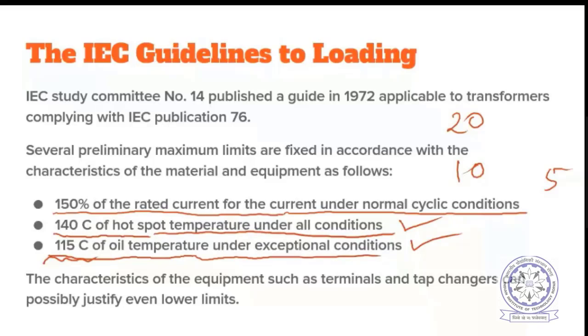the research being carried out by various labs, and the study committee investigations on this. So these are based on well-established results. The industry has to follow these to minimize the failures of the transformers. The characteristics of the equipment, such as terminals and tap changers, can possibly justify even lower limits. Due to additional effects of terminals or tap changers, a little bit lower limits can be adopted for them.